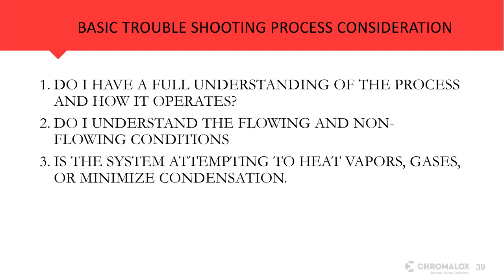Heat tracing is used for that a lot. A lot of times we see that in hoppers. If we have a lot of airflow through there, we may be taking care of the condensation or heating up the vapors and gases, but we're not actually getting quite up to that temperature. So keep those in mind whenever you're thinking about trying to troubleshoot, and you may want to get your process guys involved so that everyone's on the same page.